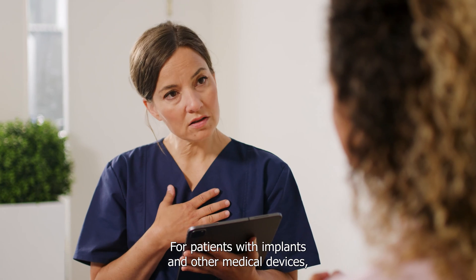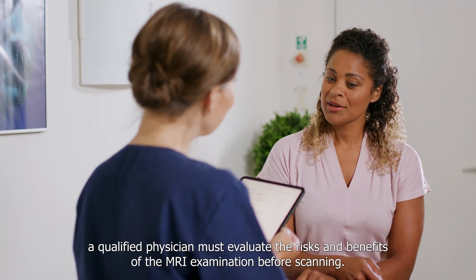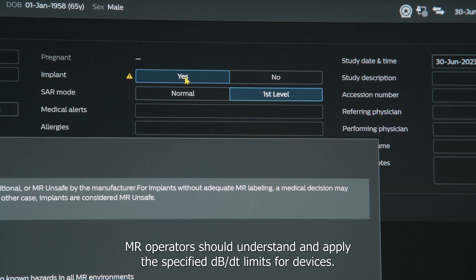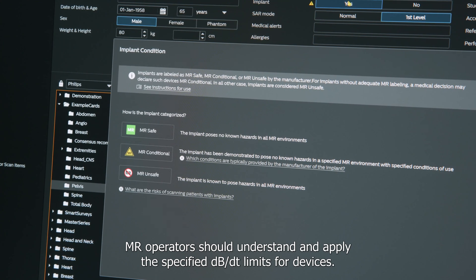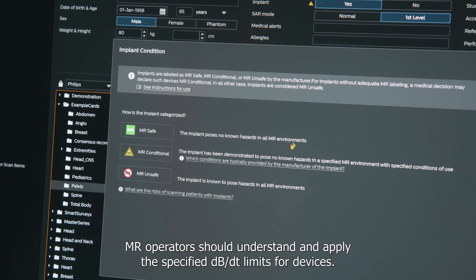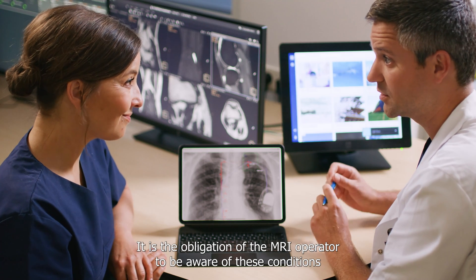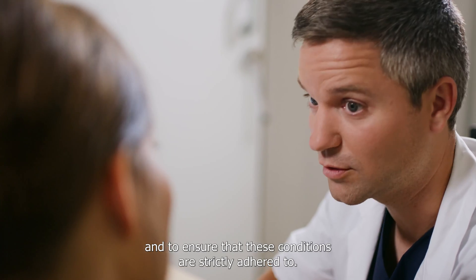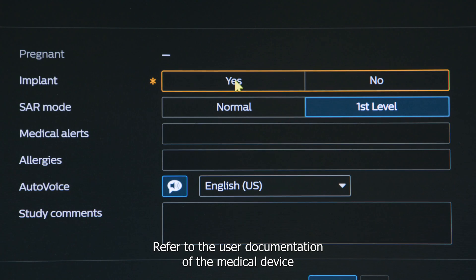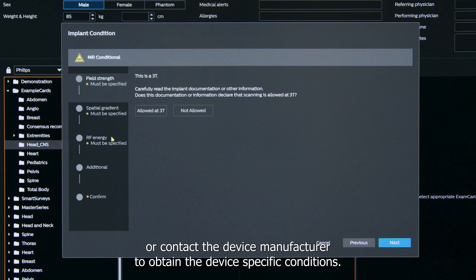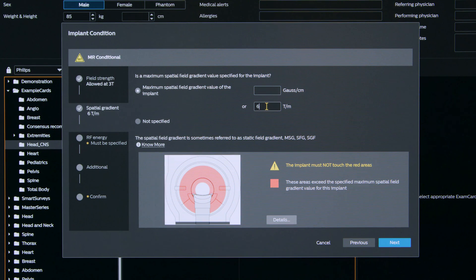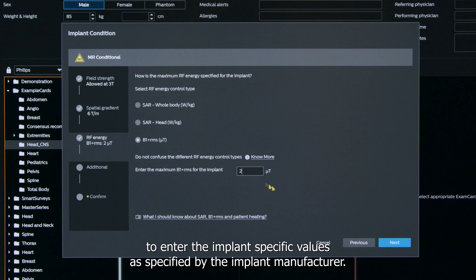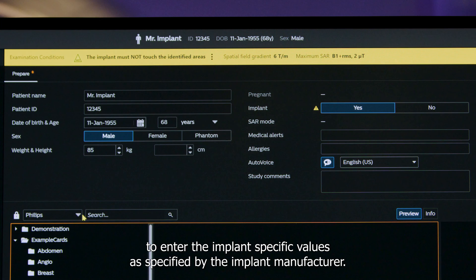For patients with implants and other medical devices, a qualified physician must evaluate the risks and benefits of the MRI examination before scanning. MR operators should understand and apply the specified dB/dt limits for devices. It is the obligation of the MRI operator to be aware of these conditions and ensure they are strictly adhered to. Refer to the user documentation of the medical device or contact the device manufacturer to obtain device-specific conditions. ScanWise Implant software provides step-by-step guidance to enter the implant-specific values as specified by the implant manufacturer.